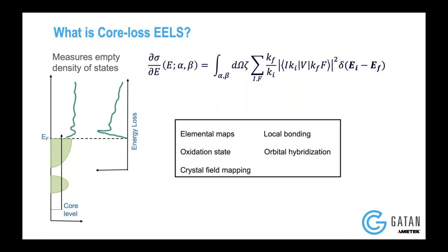You can do various types of things with this electron energy loss spectroscopy: you can measure elemental maps, oxidation state, local bonding, orbital hybridization, and crystal field mapping. Most of these applications were restricted to elemental maps before the direct electron detectors, because almost all the effects — apart from maybe the oxidation state — are very sensitive to the amount of noise in your spectrometer. That's where K3 was a very important development that happened, and it actually opened up the space even in core loss EELS.